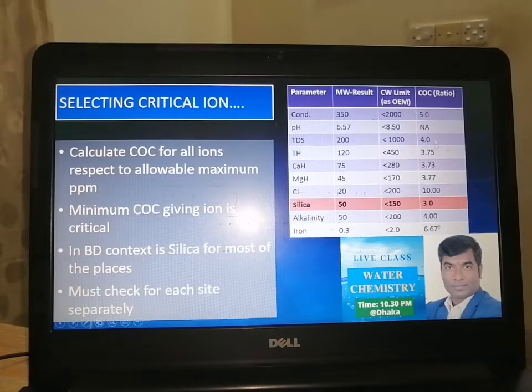So I get all the cycles of concentration from this list, and the critical ion is the one with the minimum cycle of concentration. The ion that gives the lowest cycle of concentration becomes the critical ion for this water test. Because if we cross this ratio for any other parameter, silica will automatically cross its limit and this will create scaling in the system. So that's why I have to consider the highest silica, 150, and that ratio is 3.